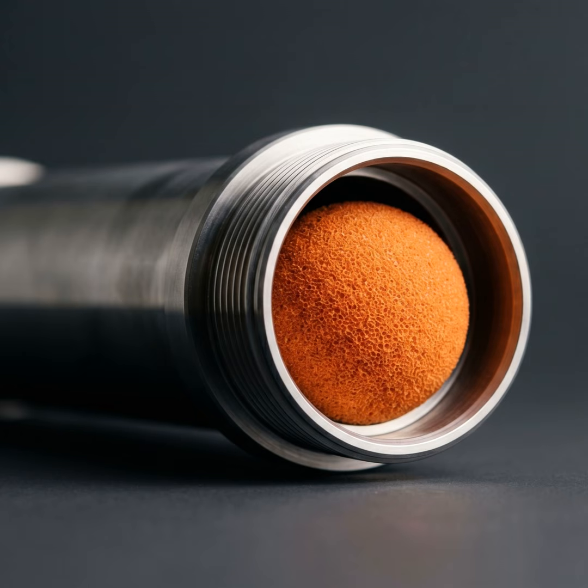So instead of running the motor at a blind 100% and physically choking the air with a metal damper, you just mathematically run the motor at 50% speed. Exactly. It uses only the exact amount of energy required to spin the fan at that specific lower speed. That is so much smarter. It is. And the true intelligence comes from the integration of the sensors. The psychrometric sensors. Right. The dynamic system monitors the temperature of the returning cooling water, but crucially, it also uses atmospheric sensors to monitor the ambient wet bulb conditions outside in real time.